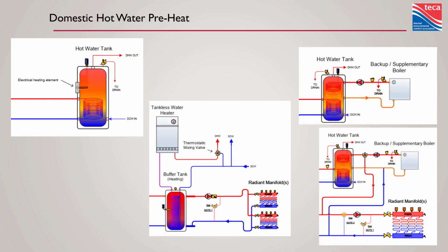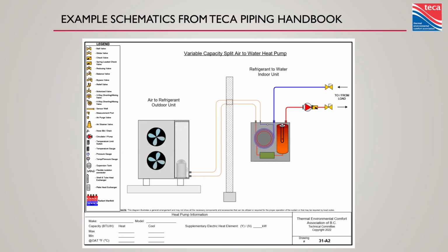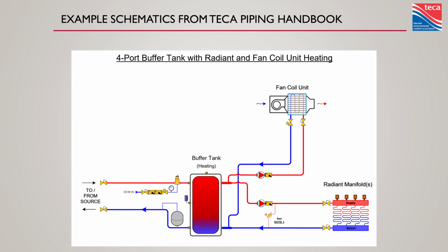So there's a lot of different ways to preheat domestic hot water and top it up with another heat source when we're dealing with hydronics. We spell all that out in the course and in our piping handbook. Looks something like this. If you've seen a hydronic piping diagram from TECA before, not much different. This is a split air-to-water heat pump. And this is what the load piping might look like. This would be a fan coil and radiant floor heating off a 4-port buffer tank.